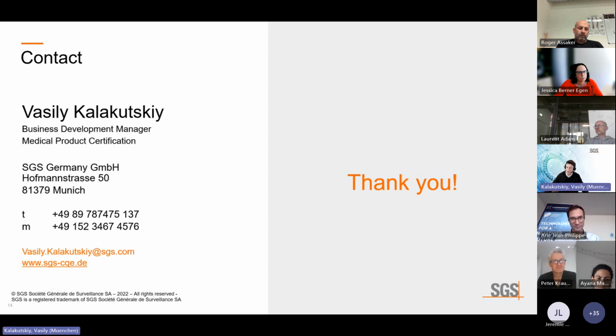I would say that regarding the conformity assessment routes available for class 2A and class 2B, for class 2A you can go a small step lower than class 2B, but everyone is doing quality management system plus technical documentation assessment. So there will not be much difference in terms of the auditing, and class 2B also has post-market surveillance. It depends upon the product, because I don't know what the product is, but it is not significantly different in general.